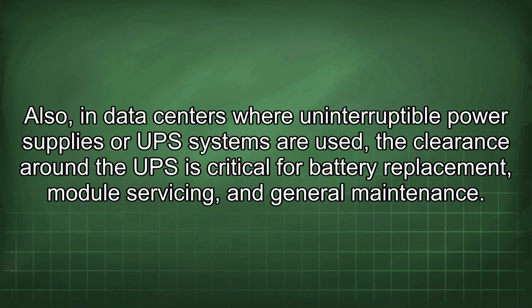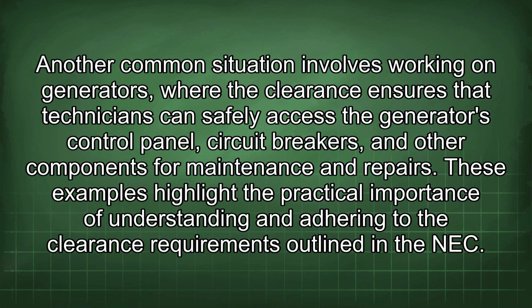Also, in data centers where uninterruptible power supplies or UPS systems are used, the clearance around the UPS is critical for battery replacement, module servicing, and general maintenance. Another common situation involves working on generators where the clearance ensures that technicians can safely access the generator's control panel, circuit breakers, and other components for maintenance and repairs. These examples highlight the practical importance of understanding and adhering to the clearance requirements outlined in the NEC.